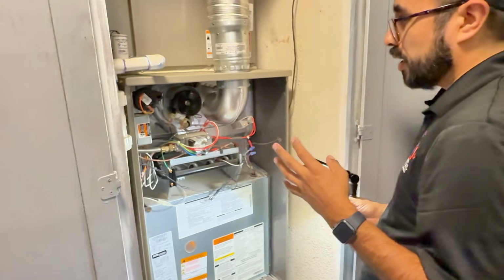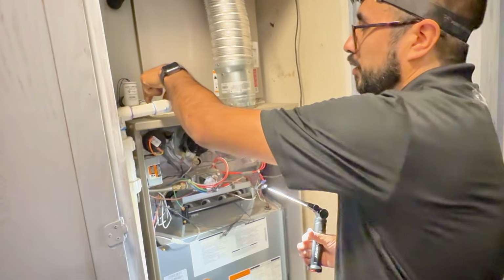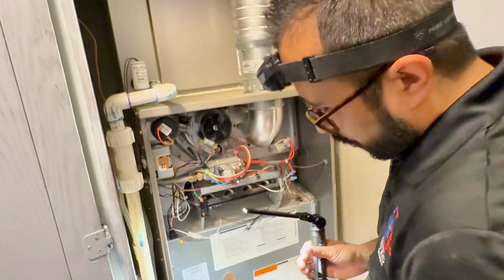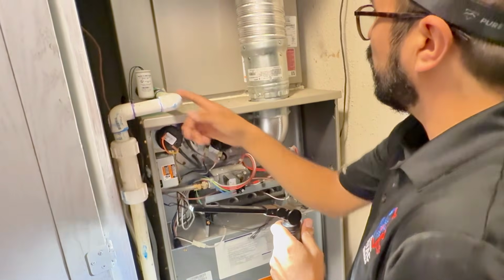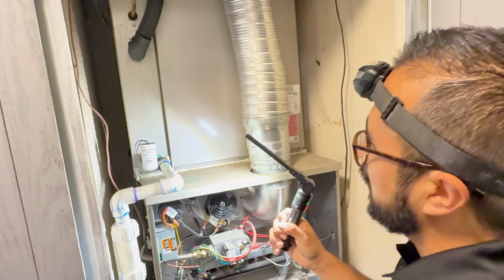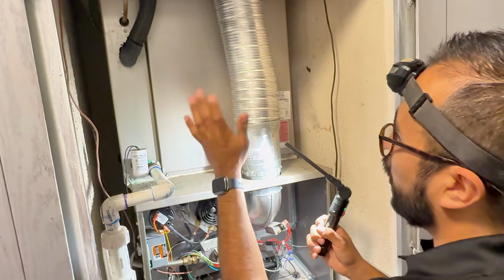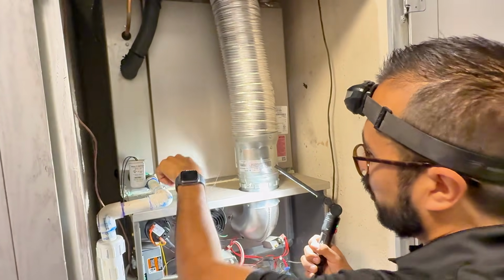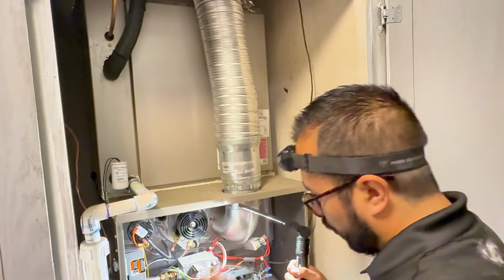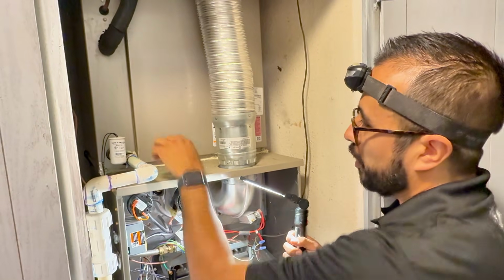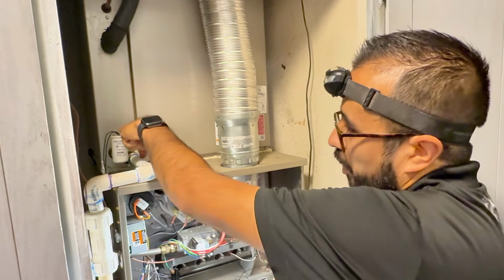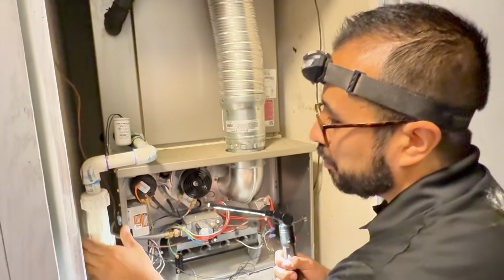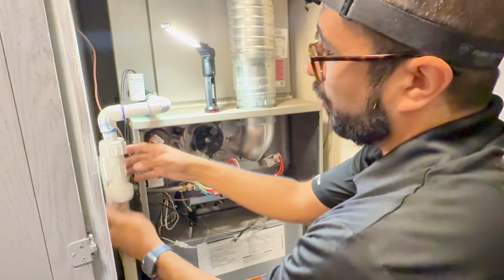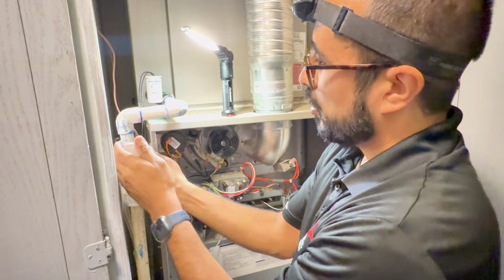The one thing you do have to check is your condensation, to see if it condensates out. They don't have a little air vent here for me. This is a blow-through, it's not on the return. If this was on the return you'd have to put a P-trap, but here you don't. Still, I want to make sure water is going out, and I believe they set it up so I could check it from here.